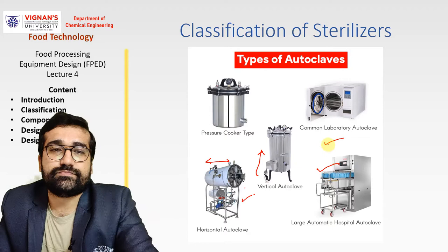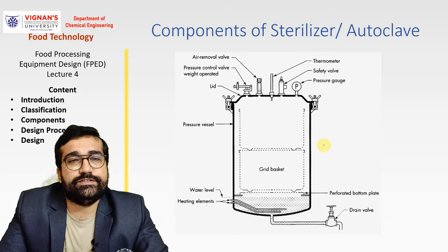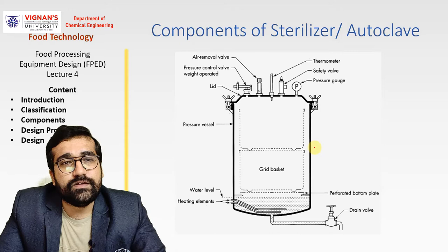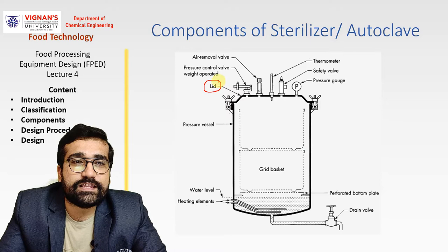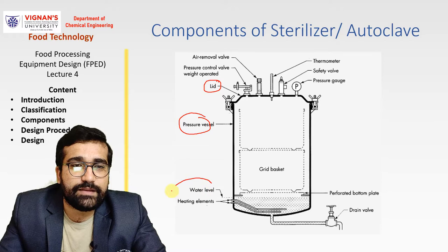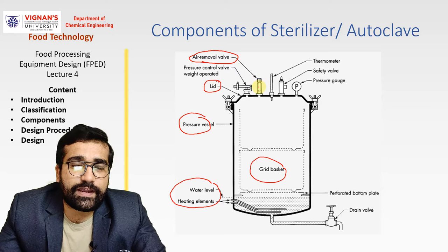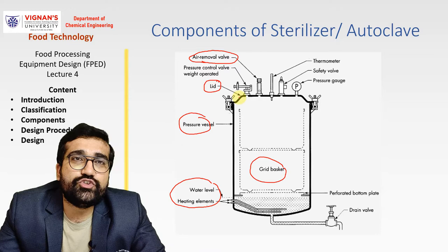So after this, we came to components of sterilizer. Before designing any equipment, we should know about the components present inside the sterilizer or in that equipment. So in sterilizer, we have so many components. The important ones are the lid, pressure vessel, then heating element, grid basket, and air removal valve.